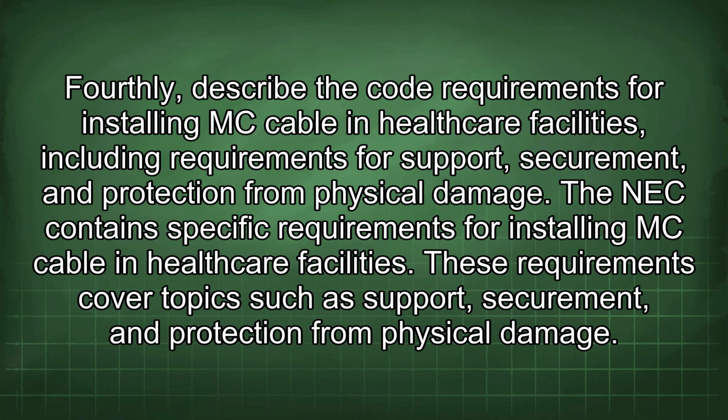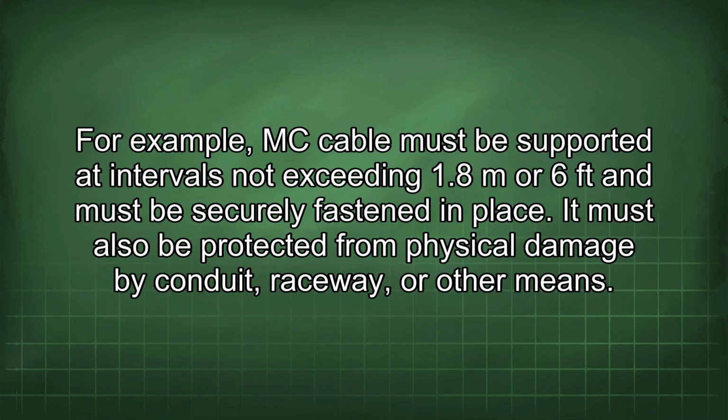Fourthly, describe the code requirements for installing MC cable in healthcare facilities, including requirements for support, securement, and protection from physical damage. The NEC contains specific requirements for installing MC cable in healthcare facilities. These requirements cover topics such as support, securement, and protection from physical damage. For example, MC cable must be supported at intervals not exceeding 1.8 m or 6 ft and must be securely fastened in place. It must also be protected from physical damage by conduit, raceway, or other means.